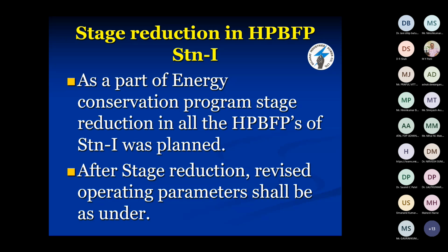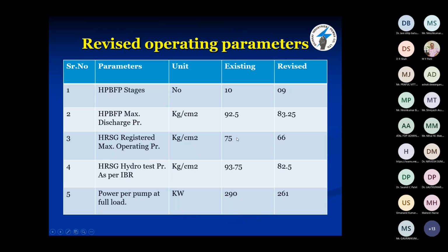Originally it is a 10-stage pump, then we have carried out the study, and ultimately we have decided that we can reduce one stage. So I will give you all the detail of that. It's very interesting. After stage reduction, revised operating parameters shall be as under. Originally the existing pump was of 10 stage. We have reduced one stage, and now it is a 9-stage pump.